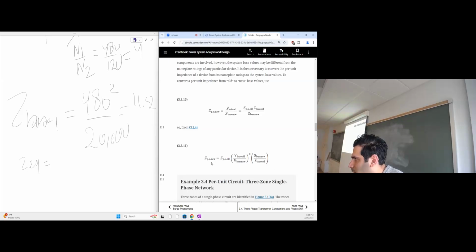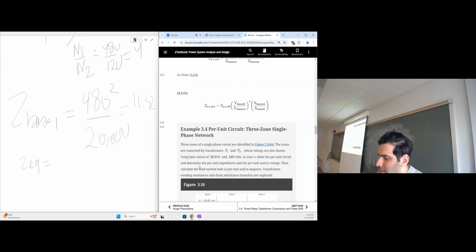Z per unit new would be Z per unit old, which is normally given, and then you multiply that by V base old over V base new squared times S base new over S base old. This is very important. You need to memorize this equation because it will be used a lot. So let's see an example of what I'm talking about.